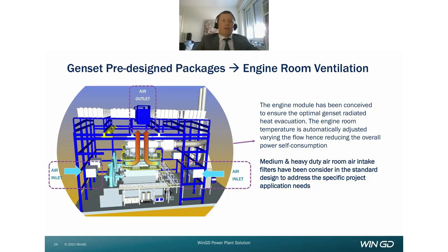The ventilation boxes are conceived to easily accommodate project-specific requirements in regard to noise attenuation and environmental conditions such as dust, proximity to the sea, etc. The genset module ventilation flow is automatically regulated to keep a constant preset temperature inside the genset hall.